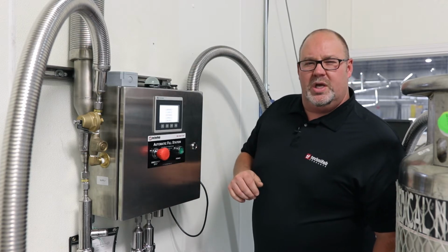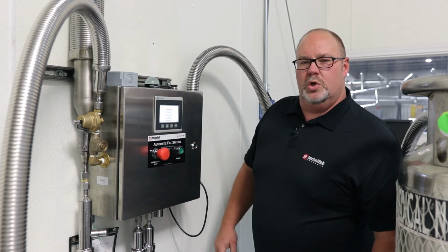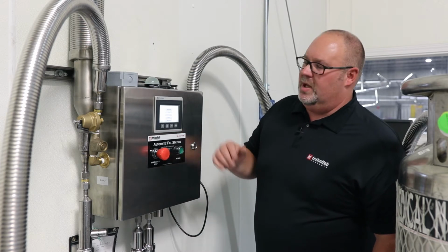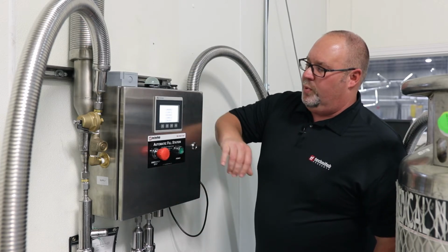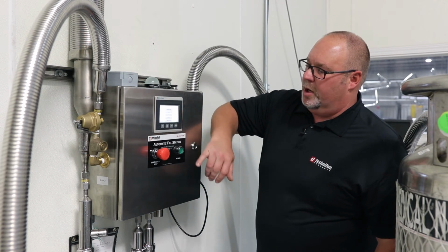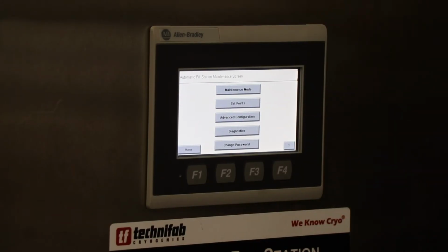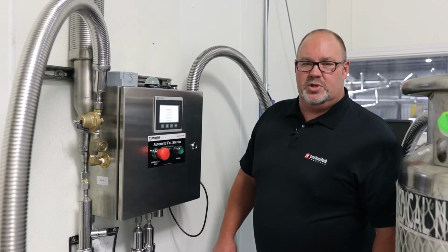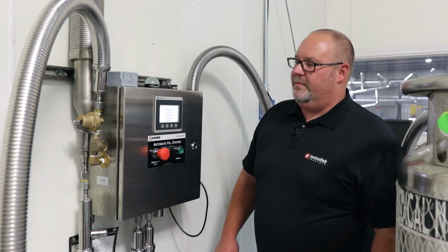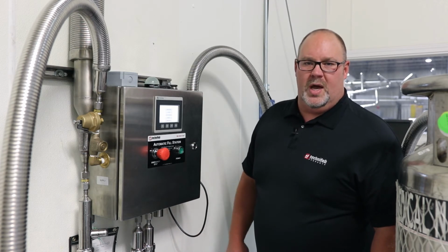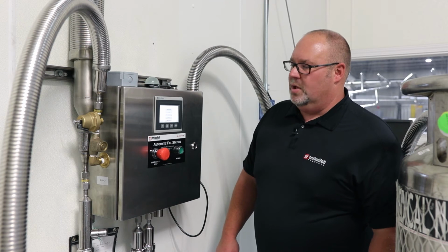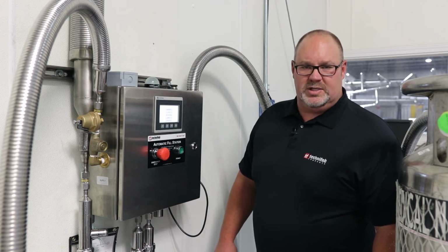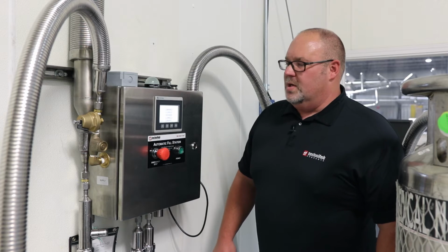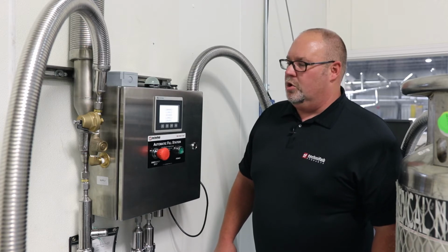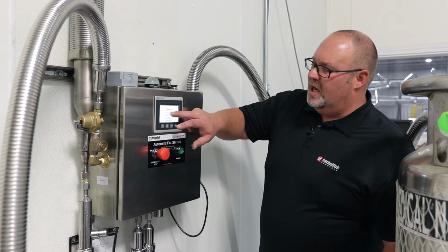Your manual will give you the username and password that could be entered to adjust the points on this screen or get into either of these two screens. The bottom three, which are advanced configuration, diagnostics, and change password: the change password is also for you, where you can edit it once you have the unit in your possession and you want to limit who has control or access to the set points. Advanced configuration and diagnostics would be used by Technifab if there was any troubleshooting needed for your particular unit. So we'll go into the set points here real quick.